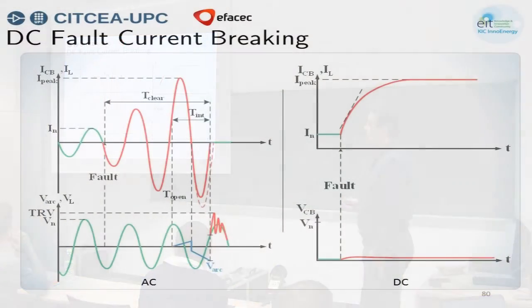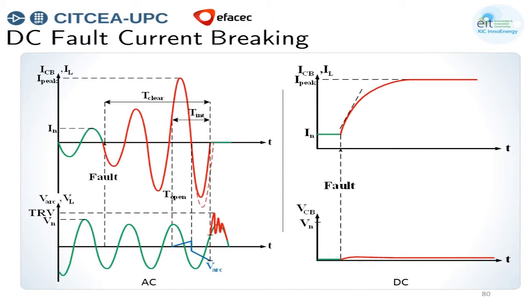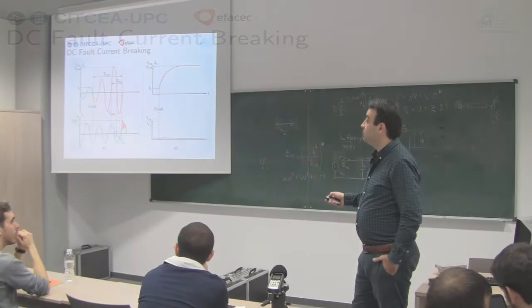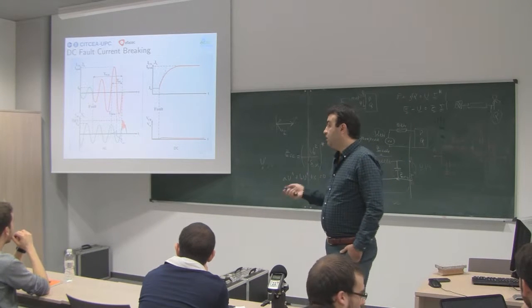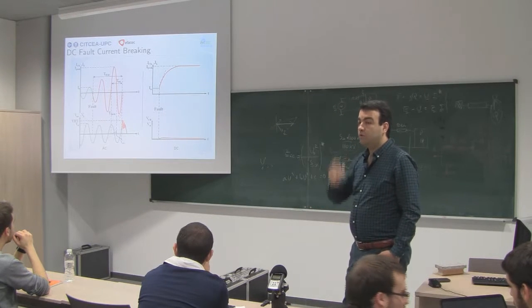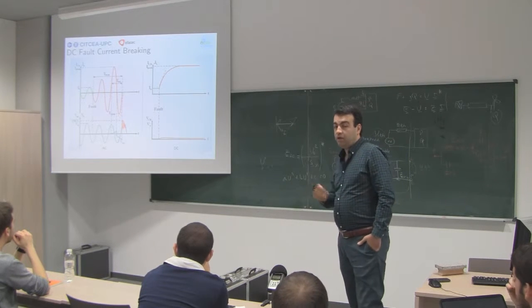Here, suppose an AC current, and at this instant we insert a fault. The fault current increases, but it crosses the zero point. If we open an AC circuit breaker, it will draw an arc, and after a few cycles, after the current crosses zero, because of the opposite voltage of the arc, the arc will be quenched. So we are able to interrupt high AC fault currents within a few cycles.